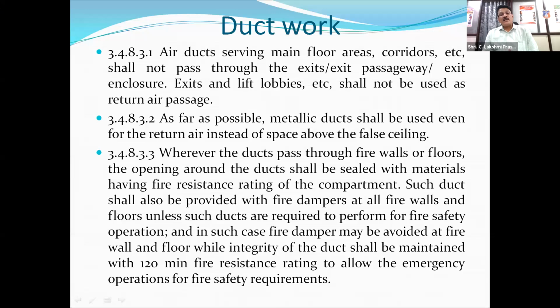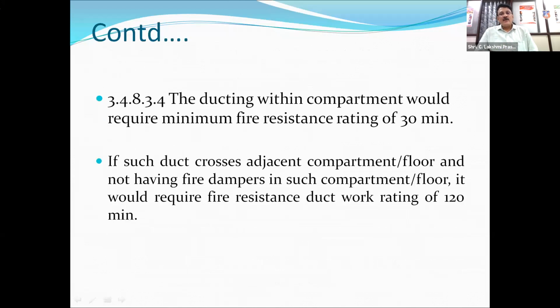the empty, unprotected false ceiling was the cause for spreading of the fire. A fire occurred in the Delhi airport a few years back, where the smoke spread through the space above the false ceiling very quickly, and 16 fire vehicles had to fight for 3-4 hours to control the fire. So these spaces are very important and need to be protected. The ducting within the compartment would require a minimum fire resistance rating of 30 minutes. Then if it is crossing a compartment, adjacent compartment or floor, then a 120 minutes fire rating has to be there.